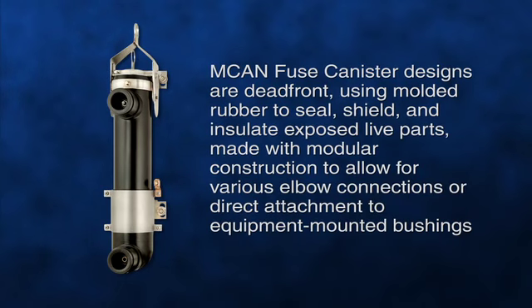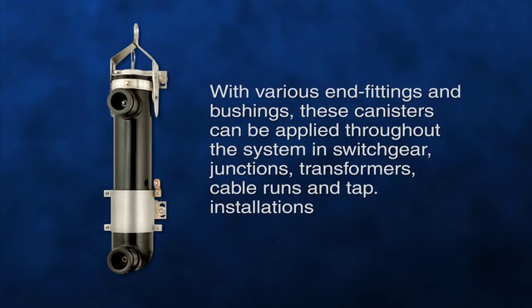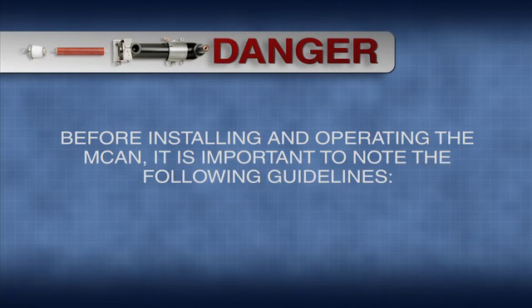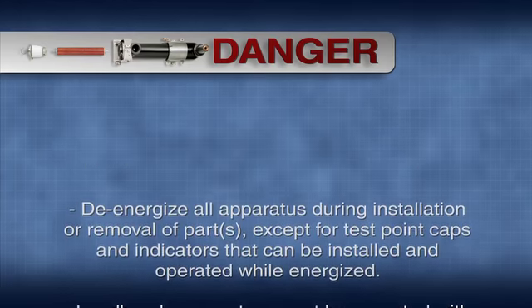Elastimold MCAN fuse canister designs are dead front, using molded rubber to seal, shield, and insulate exposed live parts, made with modular construction to allow for various elbow connections, or direct attachment to the equipment-mounted bushings. With various end fittings and bushings, these canisters can be applied throughout the system in switchgear, junctions, transformers, cable runs, and tap installations. Before installing and operating the MCAN, it's important to note the following guidelines.